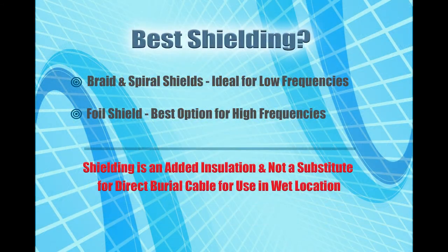The ideal shielding for any application depends on the specific application for which it is going to be used. Resistance influences shielding efficiency, thus making wire-based shields such as spirals and braid shielding ideal for lower frequency applications. Coverage is the primary issue at higher frequencies, making foil shields with 100% coverage the best option. Although shielding makes a cable more rigid and robust, it does not mean it is suitable for wet locations or direct burial unless specifically manufactured for those applications.